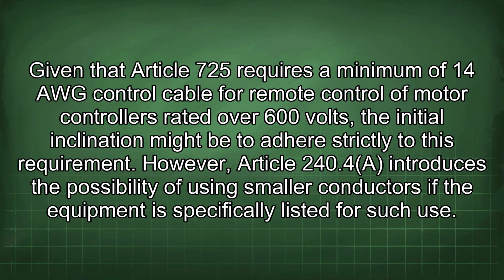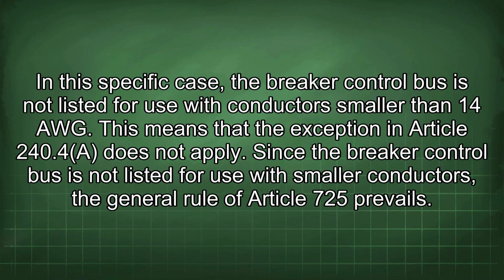Given that Article 725 requires a minimum of 14 AWG control cable for remote control of motor controllers rated over 600 volts, the initial inclination might be to adhere strictly to this requirement. However, Article 240.4 introduces the possibility of using smaller conductors if the equipment is specifically listed for such use. In this specific case, the breaker control bus is not listed for use with conductors smaller than 14 AWG. This means that the exception in Article 240.4 does not apply.